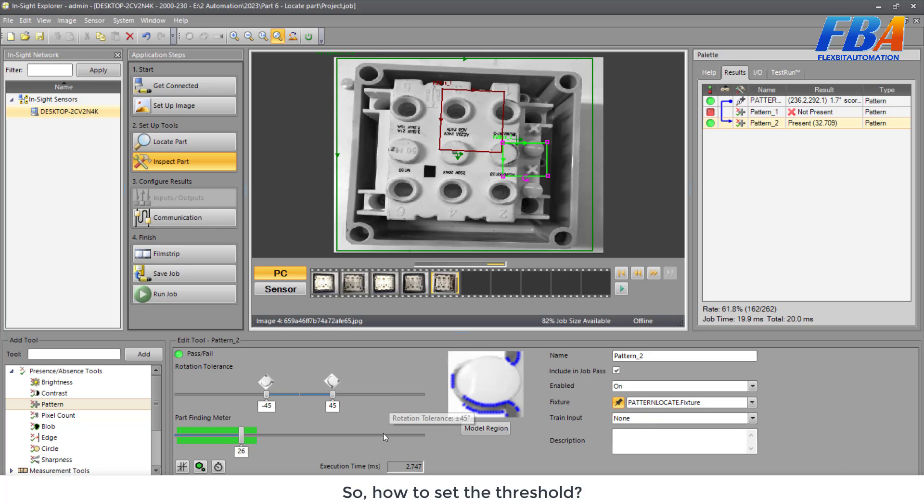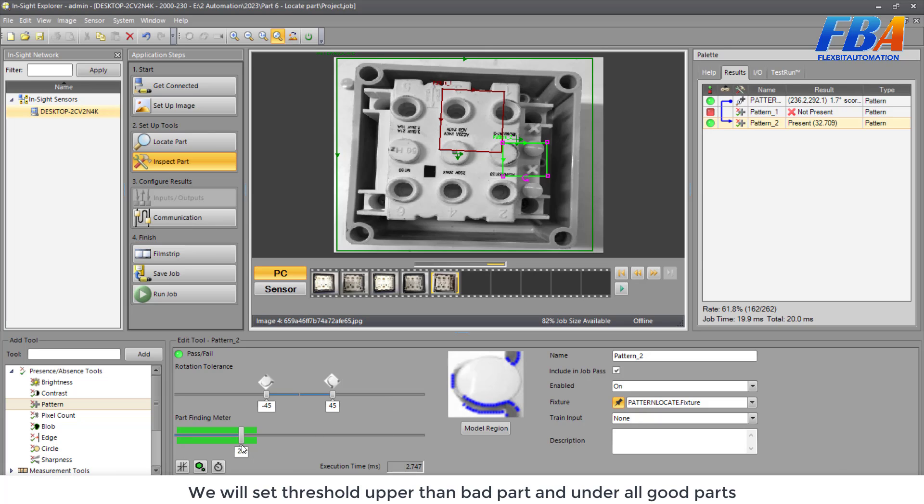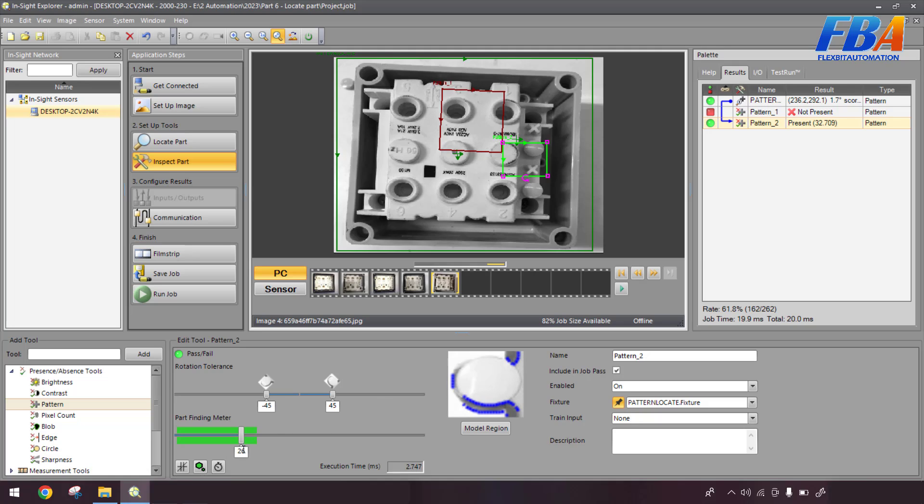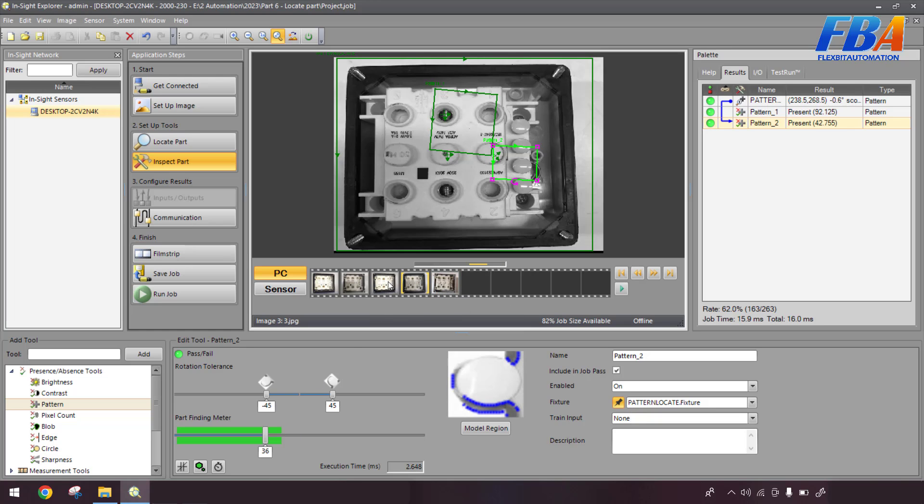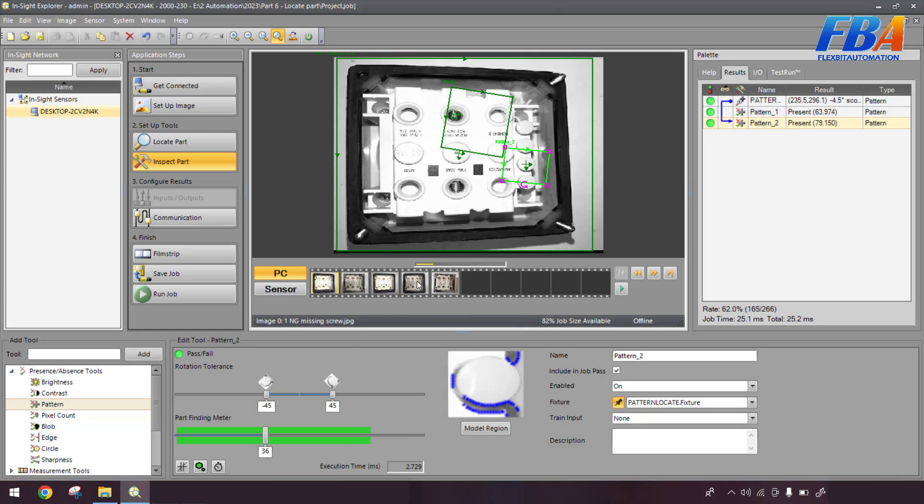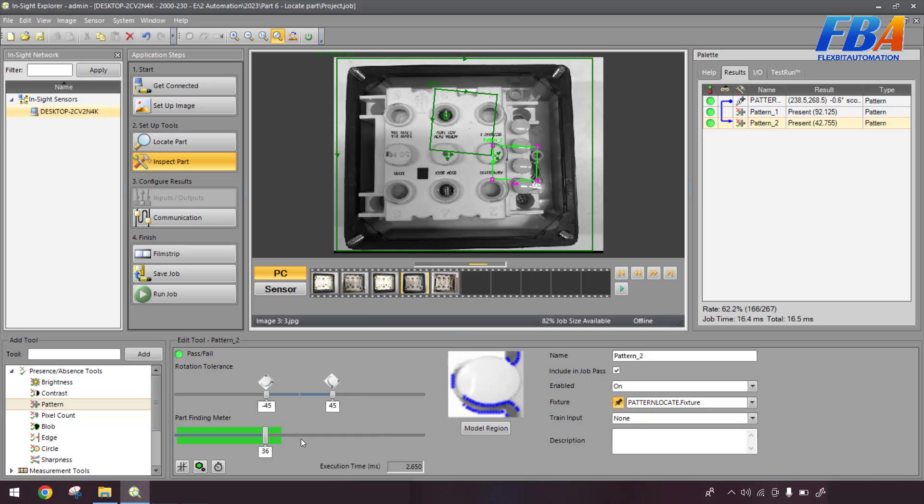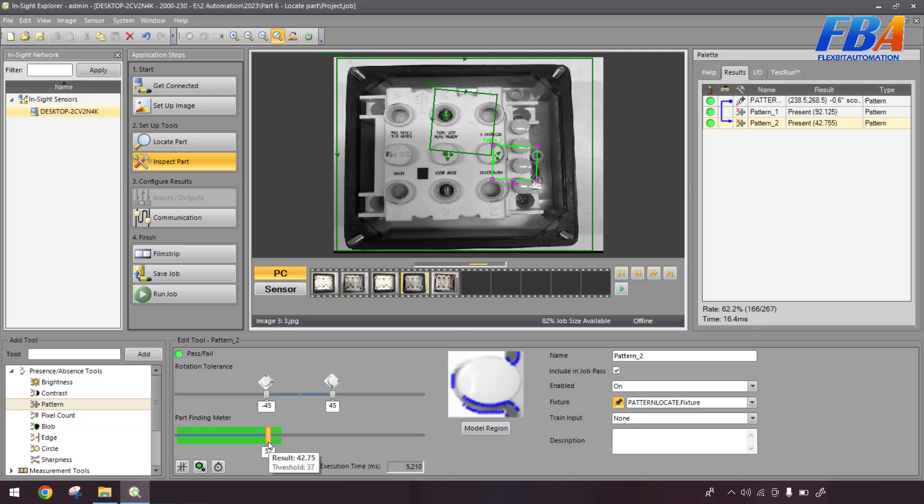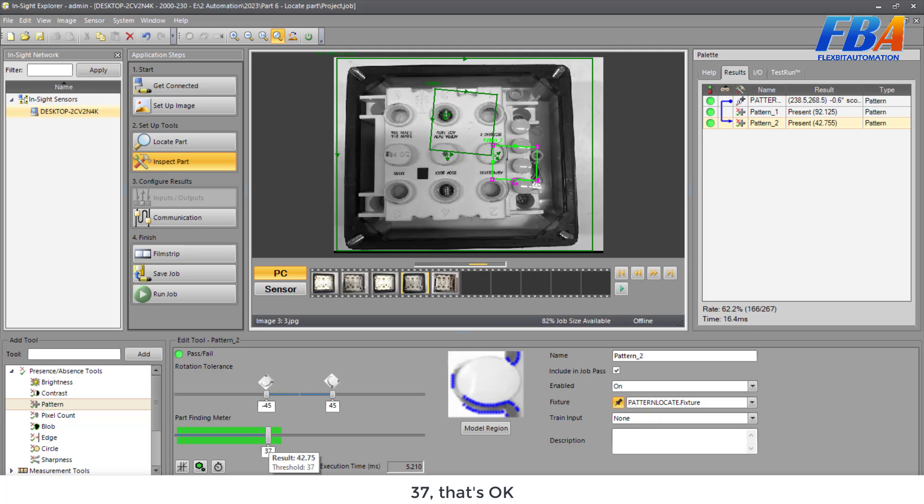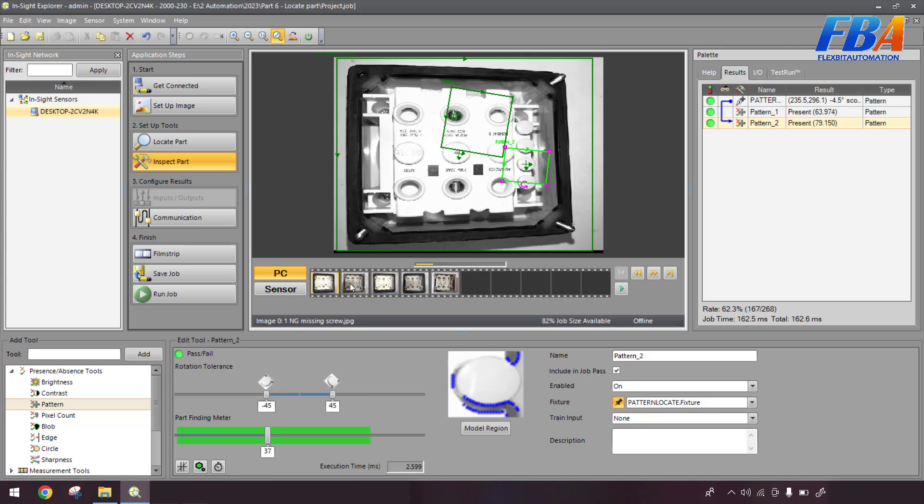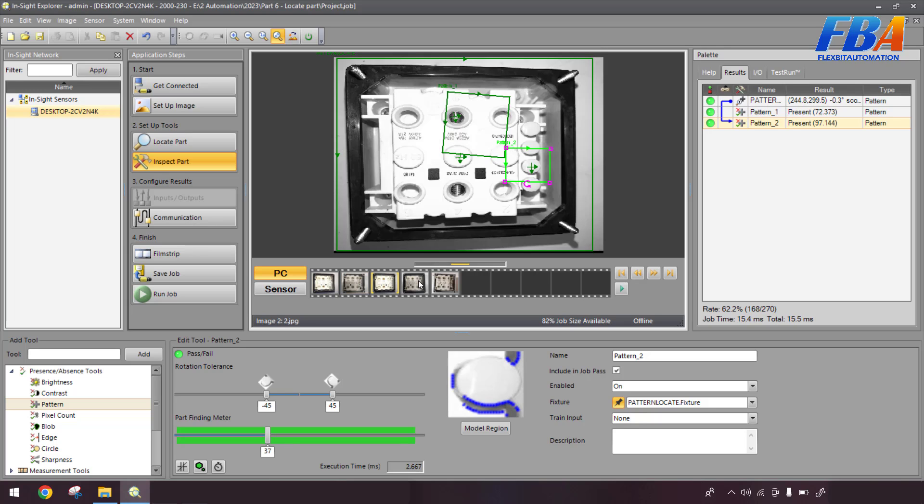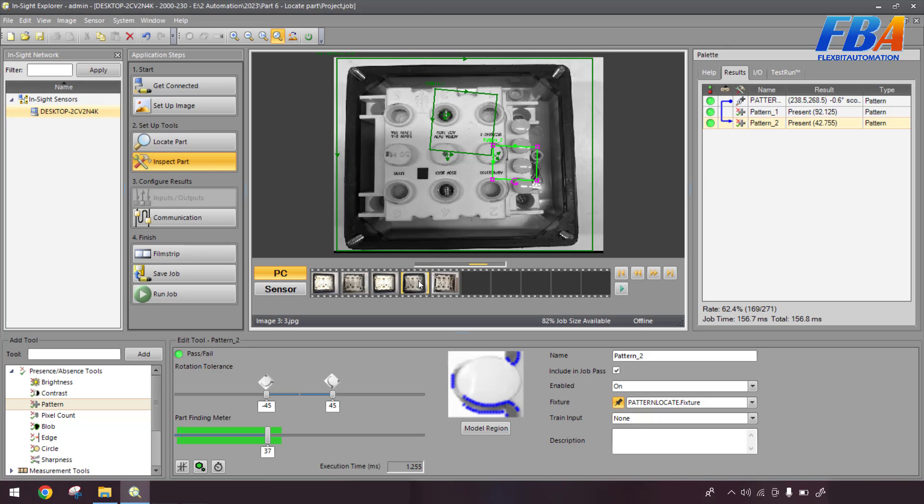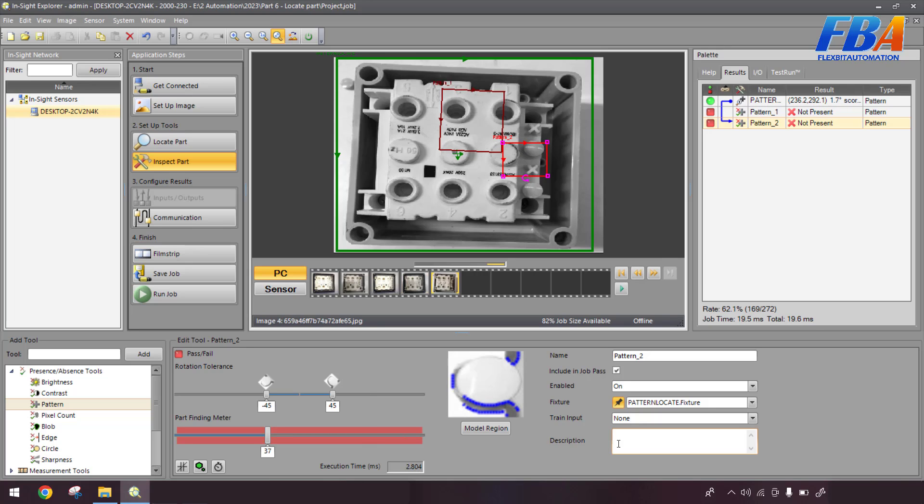So how we set the threshold. Okay, we will set the threshold upper than the bad part and under on the good part. So I will move this upper, 36. And we see the like, this part is like the sample with the lowest part finding meter results, it's the 42. So we can increase to 37. So that's okay. So now we see all the result. This good part, it's green. Good part, it's green. It's good part, so it's green. Yeah, this is also green. But this is the bad part, it's red. So our tool is correct.